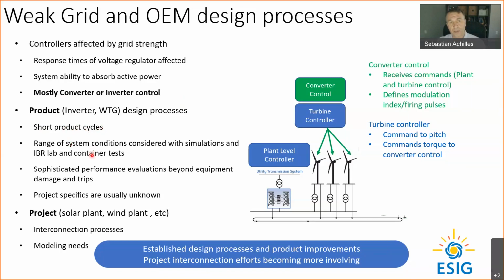The way weak grids are affecting these processes is that OEMs tend to include a large range of system conditions, including weak grids, and the idea is to simulate or test those in a lab container to make sure the converter controls and the converter in general can react, do not trip, do not get damaged, and have the type of injections in the system that are compliant with most applications. But an important point is that at the time of designing that product, you don't really know the specifics of any particular project—it's a product being designed, not a project.